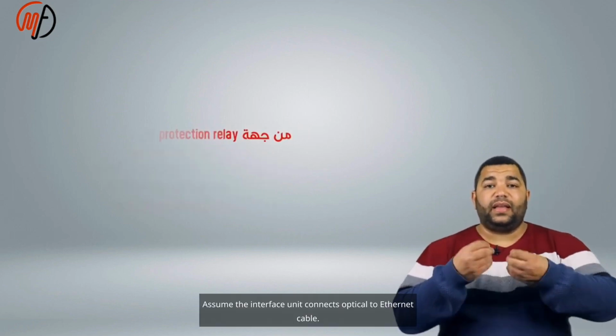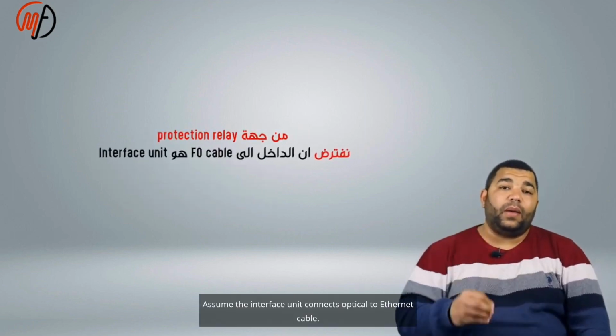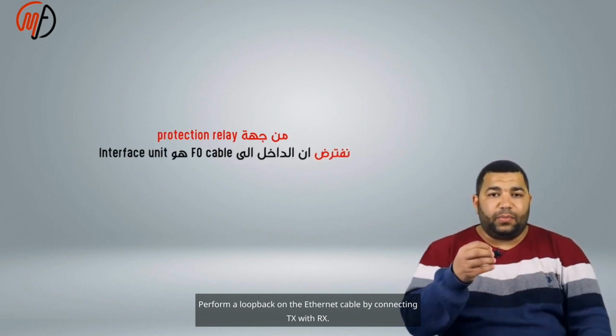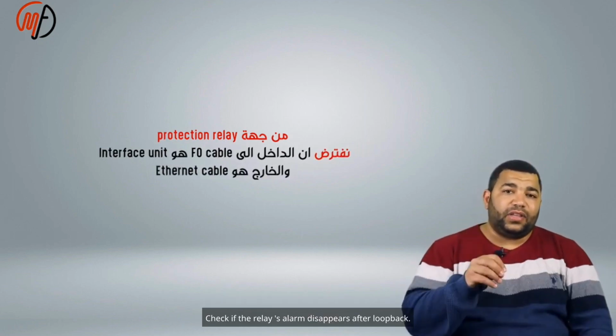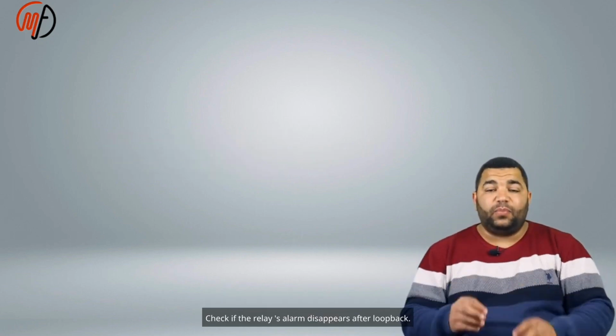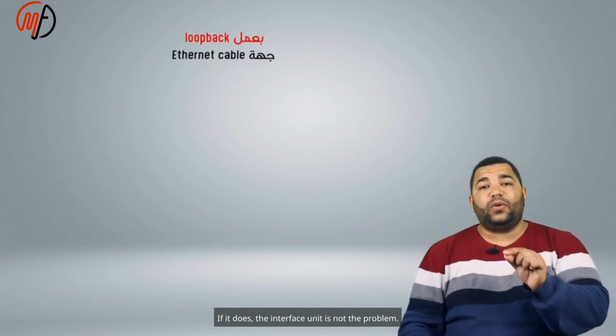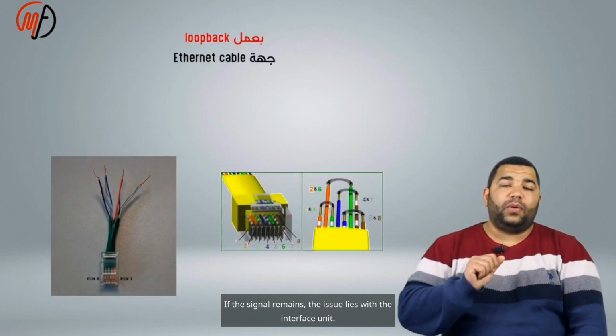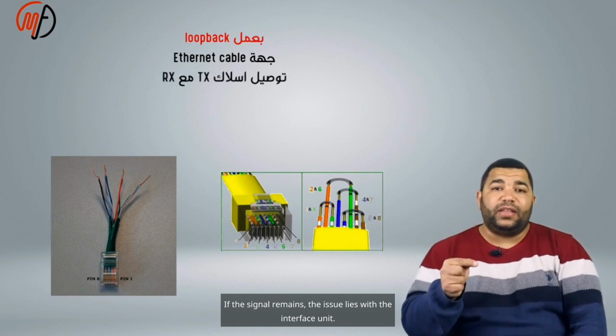Assume the interface unit connects optical to Ethernet cable. Perform a loopback on the Ethernet cable by connecting TX with RX. Check if the relay's alarm disappears after loopback. If it does, the interface unit is not the problem. If the signal remains, the issue lies with the interface unit.